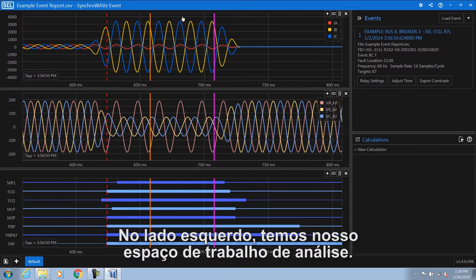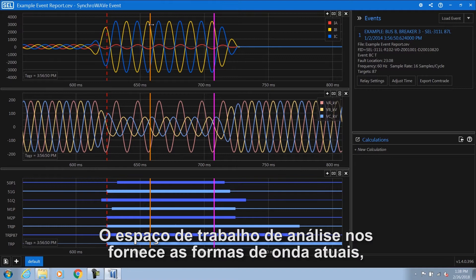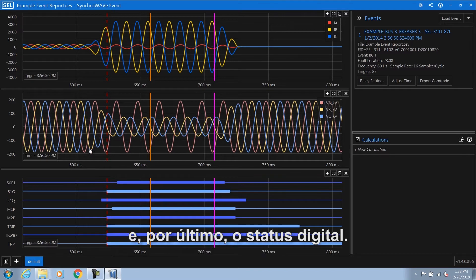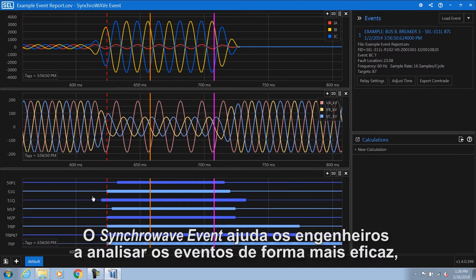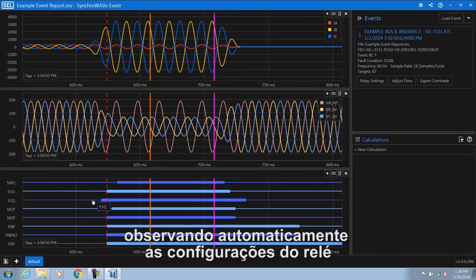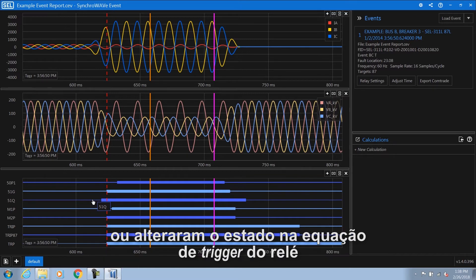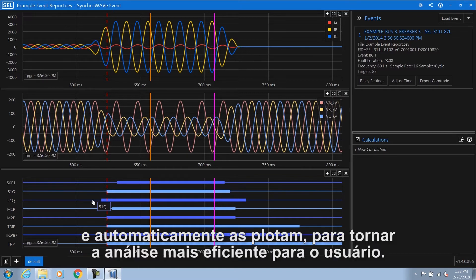On the left hand side we have our Analysis Workspace. The Analysis Workspace provides us the current waveforms, followed by the voltage waveforms, and lastly the digital status. SynchroWave Event helps engineers more effectively analyze events by automatically looking at the Relay settings and the trigger equation, detecting any digitals that asserted or changed state in the Relay trigger equation, and plotting those automatically for the user to make analysis more efficient.